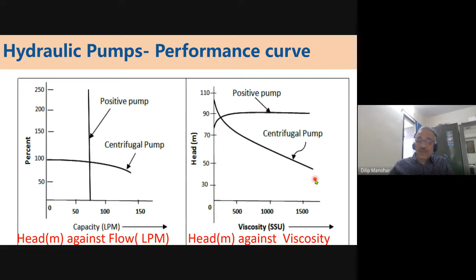Now I've given here some small calculation to illustrate how easy it is to do the pump calculation of theoretical flow rate. A gear pump has an outside diameter of 80 millimeter, inside diameter of 55, width is 25. The actual speed is 1600 rpm. The rated pressure is 95 bar. So calculate volumetric displacement and theoretical discharge.